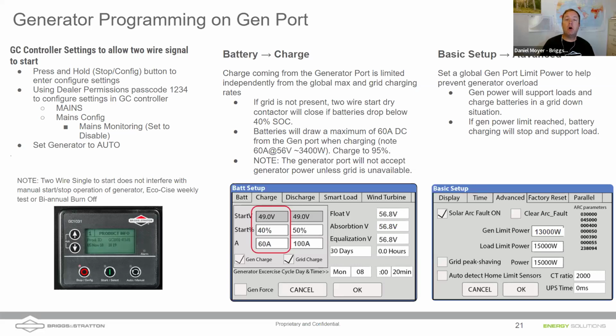What we need to do is go into the GC 1031 controller on the generator and reprogram it so that if it still sees the presence of grid, go ahead and start if you get the two-wire signal to start. If you don't do this and the generator sees that two-wire signal to start, it's not going to start. So this is important, to be able to get in there and change the configurations. As Nathan mentioned, I'm sure this is capable on other brands of generators as well. Nathan, do you want to talk us through the middle portion?